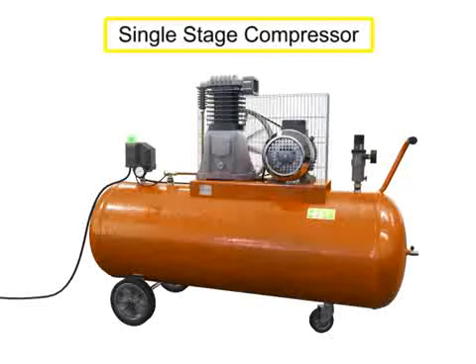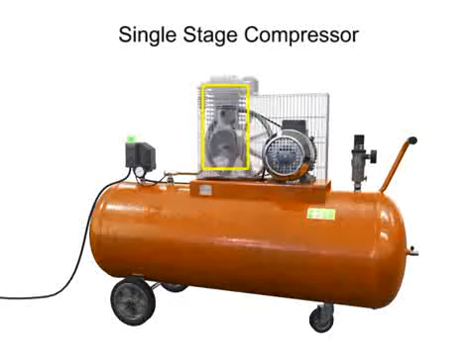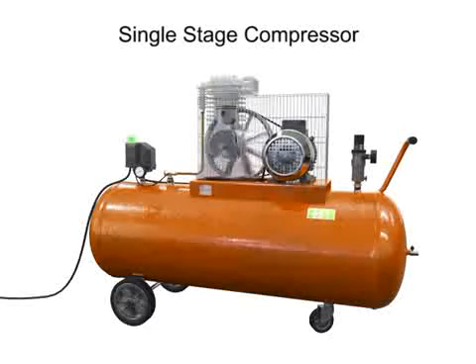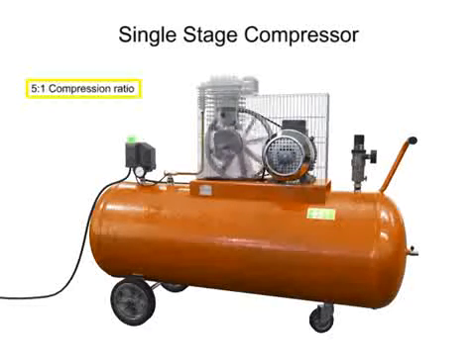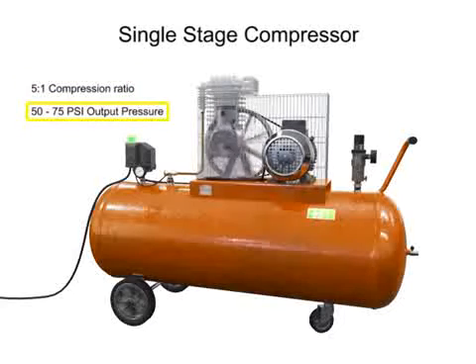This is a single-stage compressor. It has only one piston and cylinder and compresses the air in only one stage. A single-stage compressor typically has a compression ratio of 5 to 1 with an output pressure of about 50 to 75 PSI.